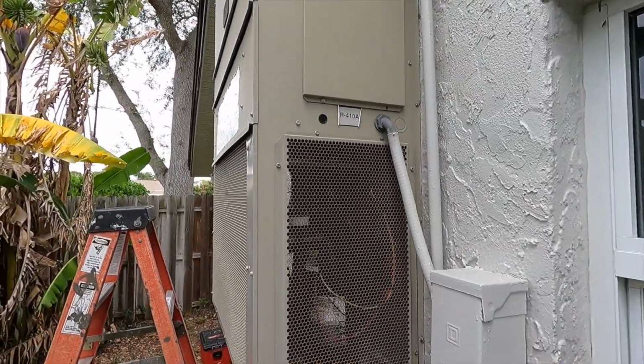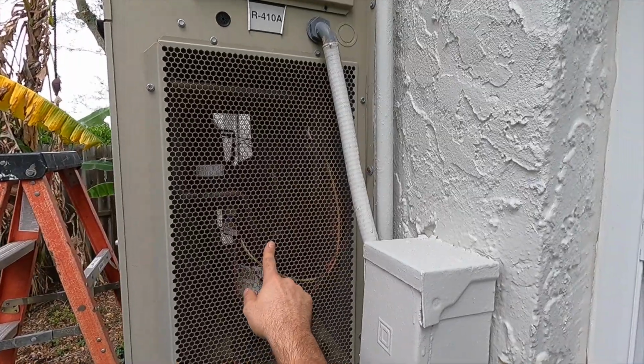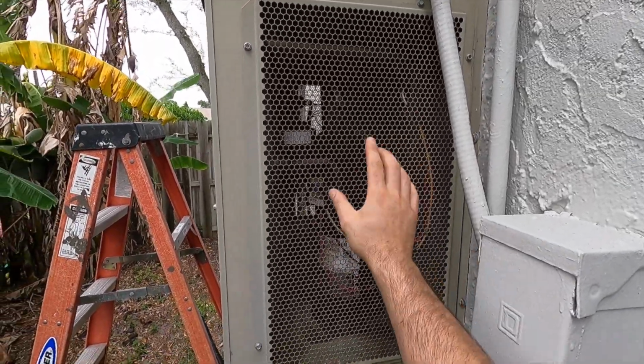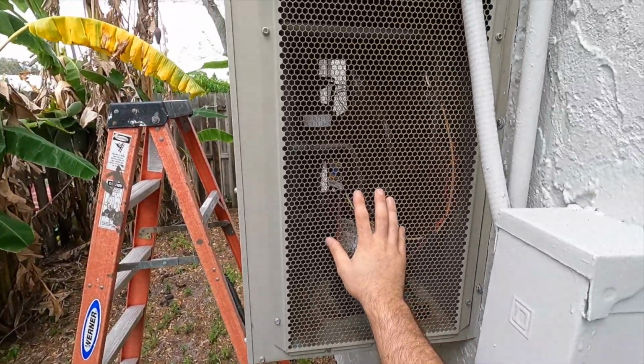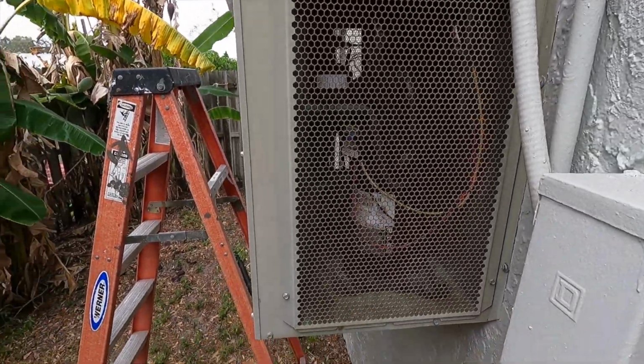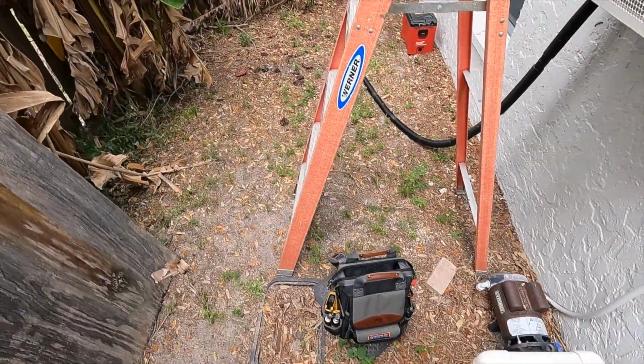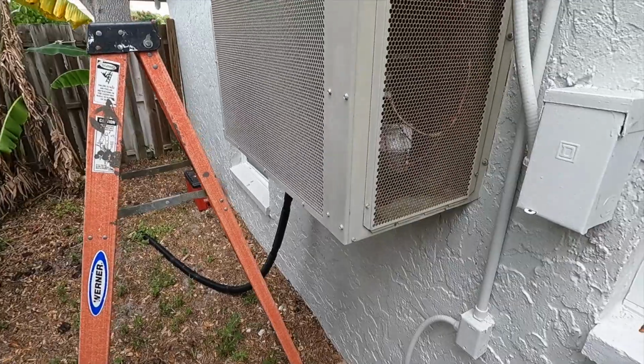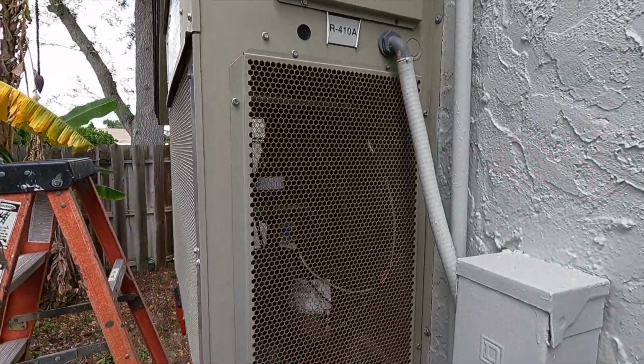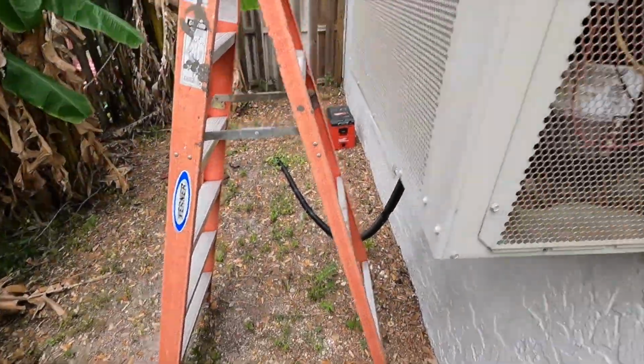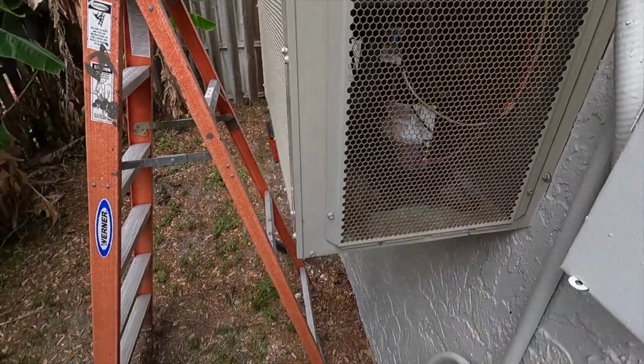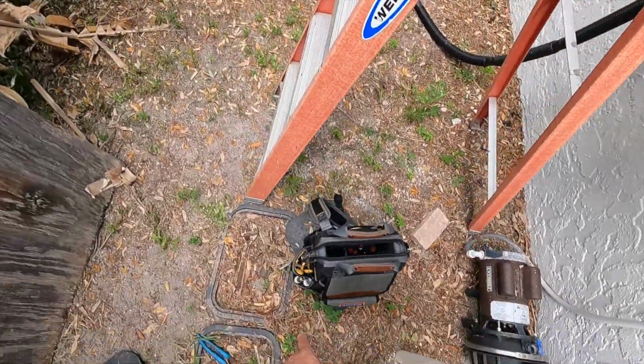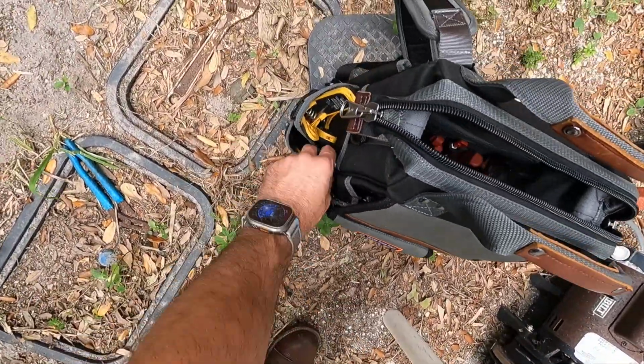Quite noisy over here, but we got our refrigeration checks here, our valve for our liquid line and our suction line. We're going to go ahead and remove this panel here so we can access them and check the charge. On this package unit, temperatures aren't nearly as important, simply because superheat and subcool on a package unit is not typically something you're looking for, but we'll throw them on there either way. So we're going to go ahead and get our probes and our clamps.